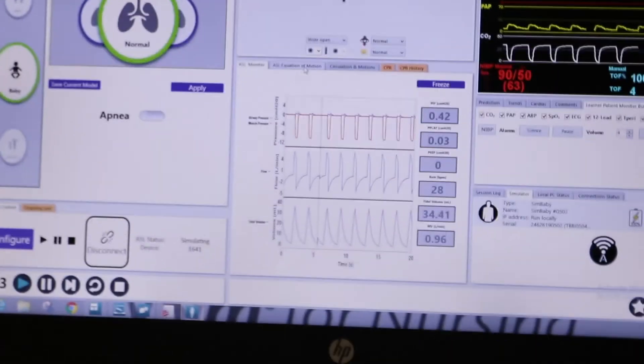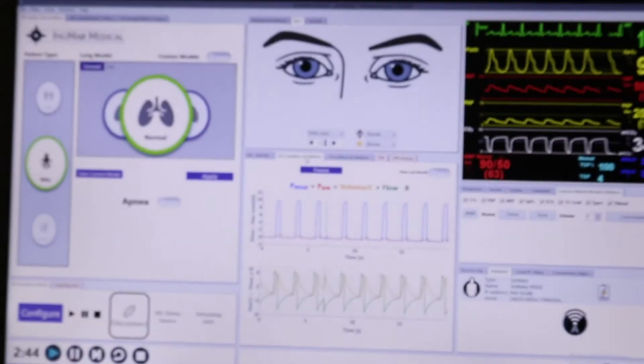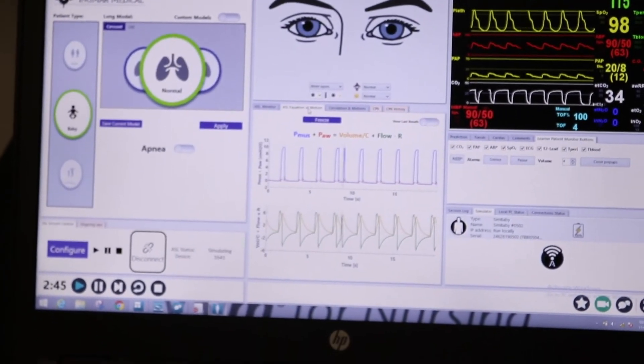It connects nicely onto a ventilator and it's got a piston-driven lung which allows you to change the resistance in each lobe of the lung or as a whole. And you can see if you look down, we've got the traces showing your flows and tidal volumes, and then we've got the equations of motion that you can use as well for teaching purposes.